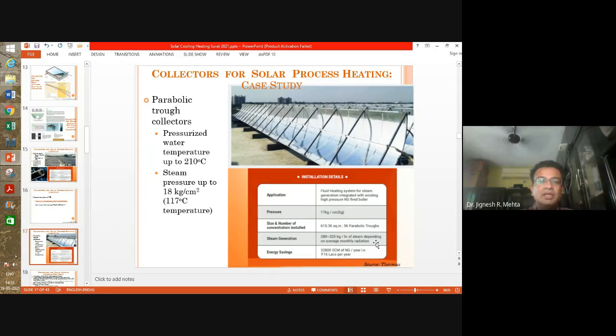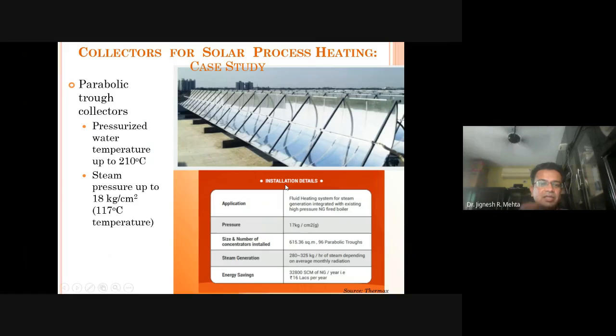So as you can see here, it is used for the application at 210 degree Celsius, and the steam pressure is 18 kg per centimeter square, right? And one such plant installation details: fluid heating system for steam generation integrated with existing high pressure natural gas fired boiler. So it is to some extent replacing the natural gas. Of course, you cannot depend 100% on the solar, because there could be many cloudy days, as well as at night you don't get insolation, solar radiation at all. Again, early morning and late afternoon or evening hours, you don't get the solar energy.